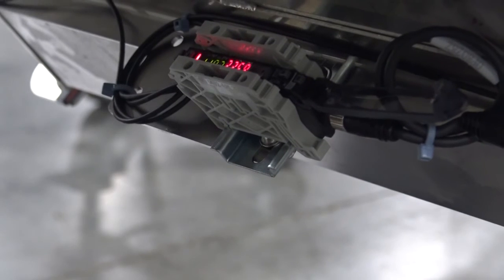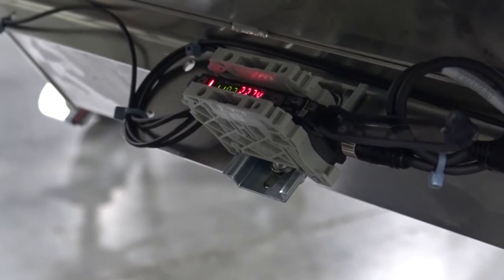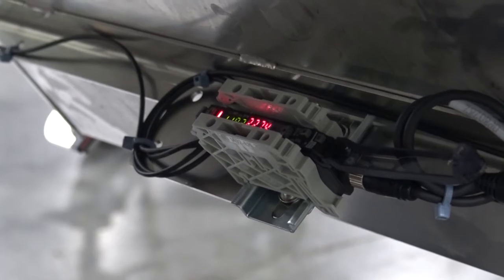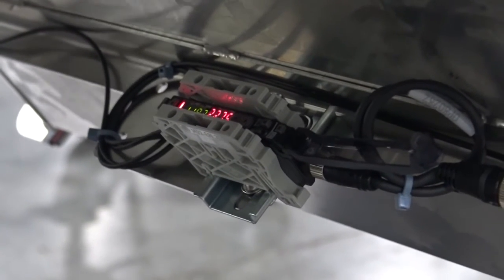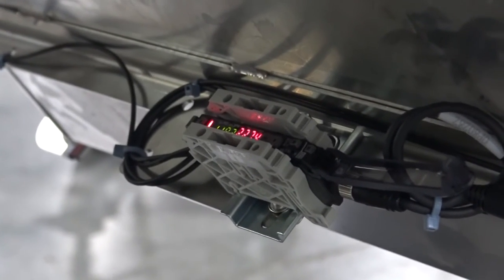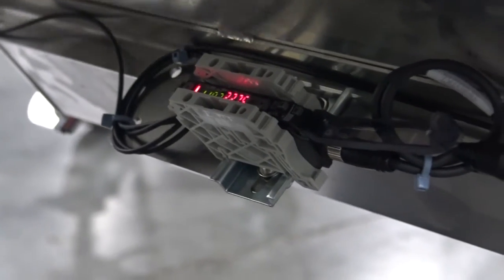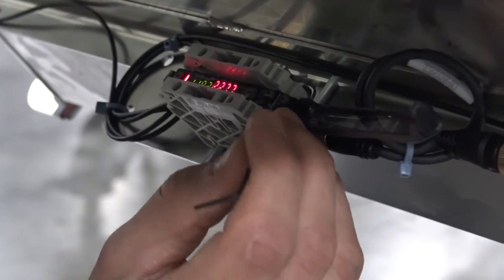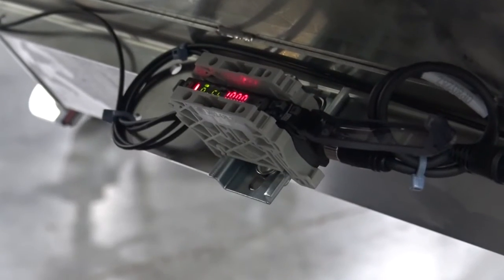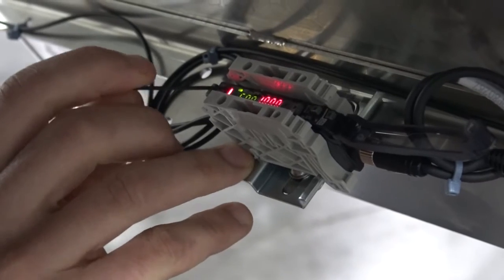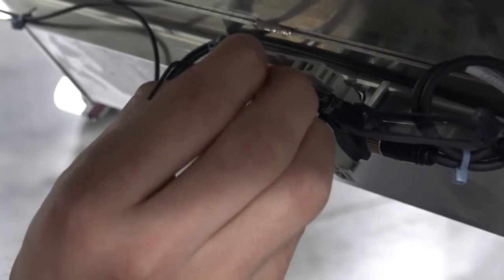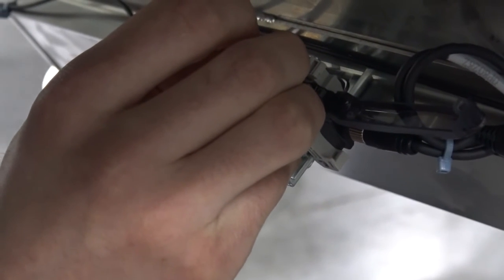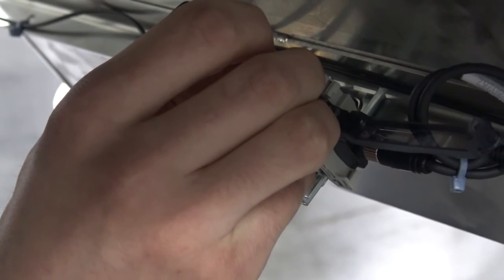So now I want to set that threshold to 100 just to get an easy reference number to work from. According to the procedure, press the preset button once, and that's right here all the way on the right. So now we're at 100, and our trip value is set automatically to 50, and we recommend to bring that up to about 80. So we're going to trip at about 80% light. Now we're working in percentage.